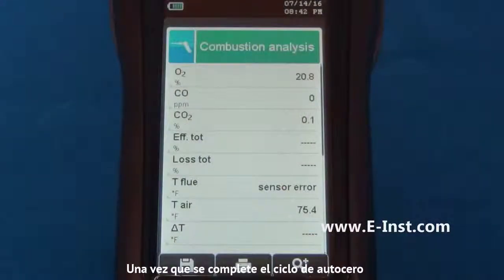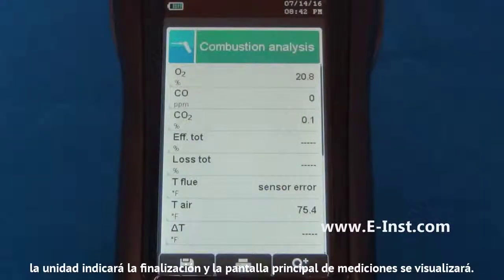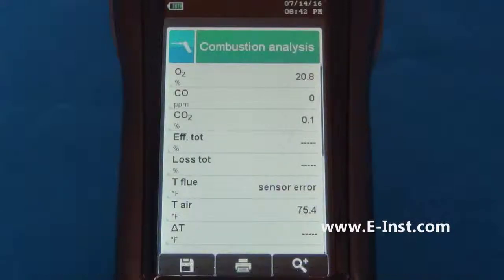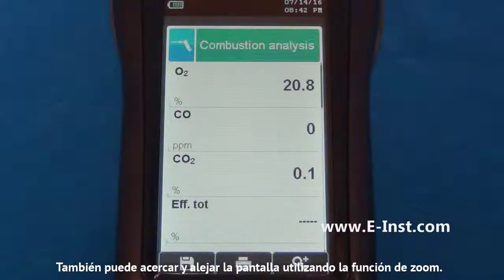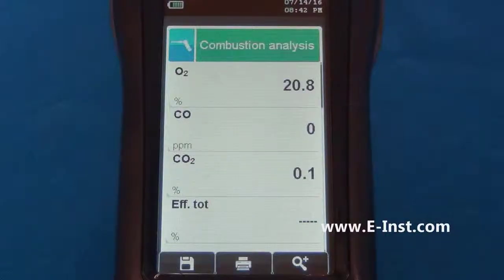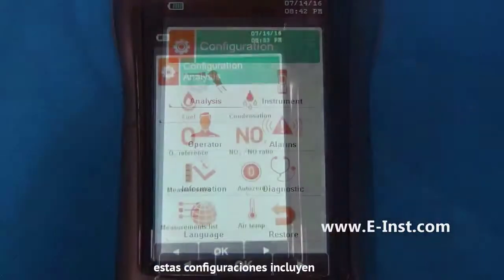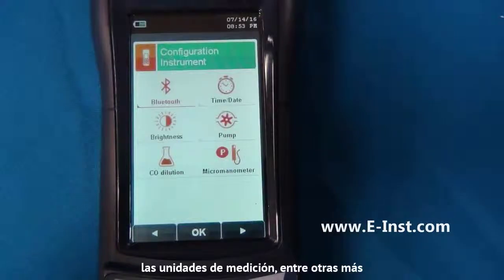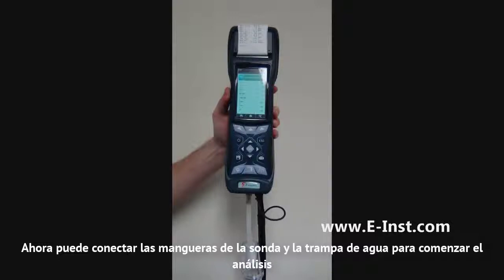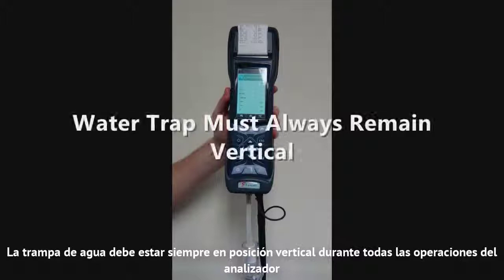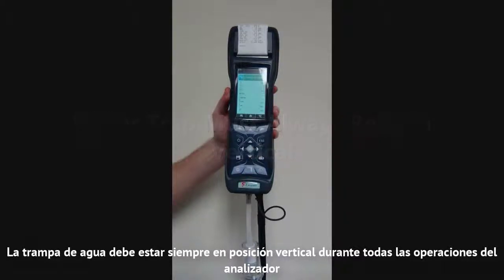Once the AutoZero cycle is completed, the unit will indicate the completion and the main measurement screen will be displayed. You can also zoom in and out on the screen by using the zoom function. Next, go to the setup menu to make sure the settings are correct. These settings include fuel selection, time and date, measurement units, and several more. Now you can plug in the probe hoses and water trap to begin the analysis. The water trap must always be in the vertical position during all operations of the analyzer.